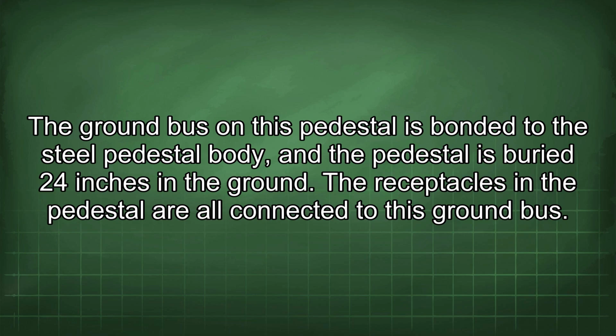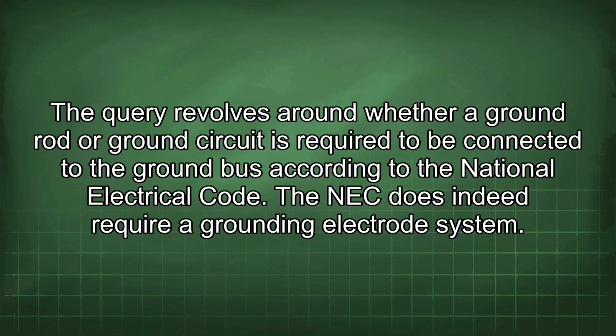The ground bus on this pedestal is bonded to the steel pedestal body, and the pedestal is buried 24 inches in the ground. The receptacles in the pedestal are all connected to this ground bus. The query revolves around whether a ground rod or ground circuit is required to be connected to the ground bus according to the National Electrical Code. The NEC does indeed require a grounding electrode system.